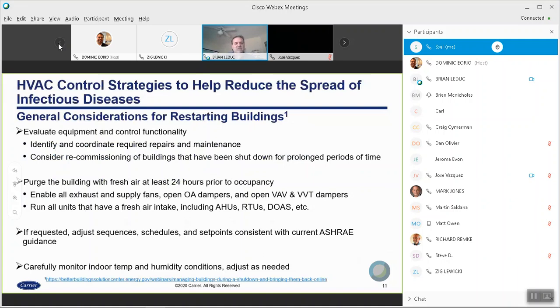Okay, now restarting, there's probably a little more information here that might be of great use. If a building's been shut down for a considerable amount of time, you want to make sure the equipment and the controls remain functional, identify and coordinate any required maintenance or repairs, even so far as to recommend recommissioning of a building that has been shut down for a prolonged period of time. One of the key requirements or pieces of guidance from ASHRAE is going to be increasing ventilation. And obviously, if your economizers are not working correctly, if the inlet grills have gotten plugged or anything, you're not going to be able to ventilate, period, increase ventilation.